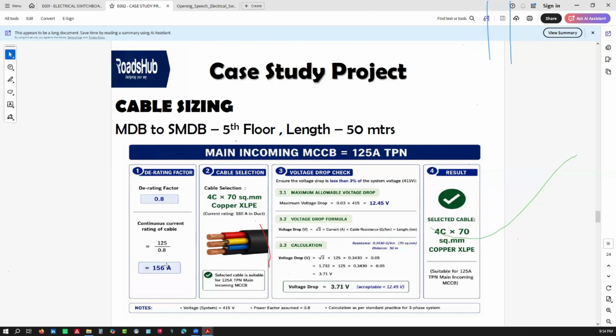Derating factor, we divide it. So you have a 156 after you consider the derating factor. And then from there, you need to go to your tables, because every catalog table will actually help you to come up with the appropriate cable size.